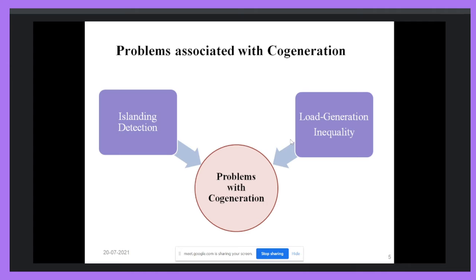So the industrial system will also contribute to that fault current. If the industrial system does not separate in time, then the system will be unstable along with the grid. As the grid becomes unstable, the industrial system will also become unstable. So to maintain stability in the industrial system, we have to separate it, and this separation is called islanding. So islanding detection is also an issue.